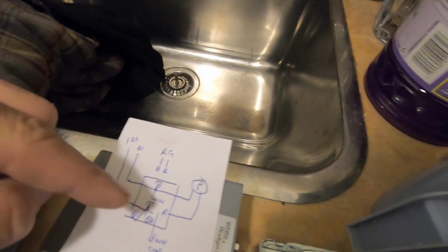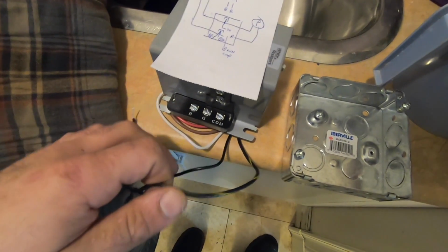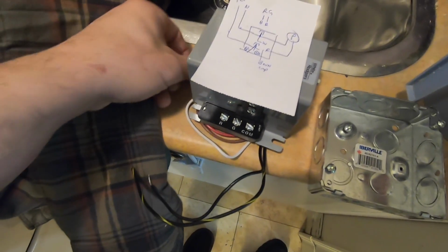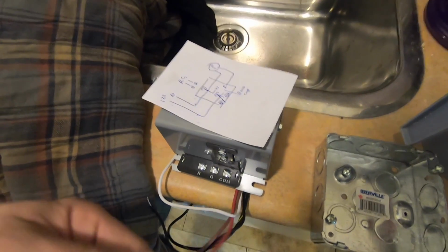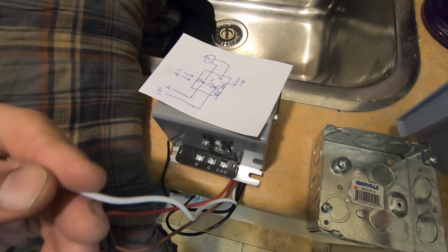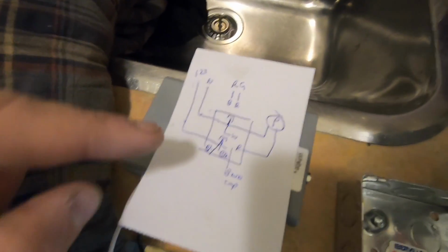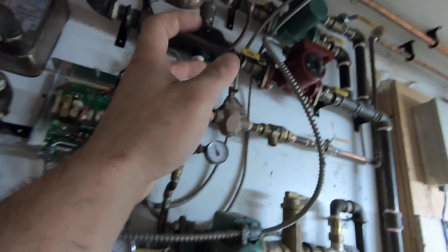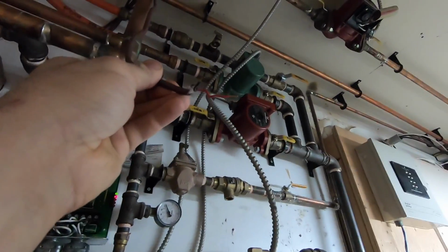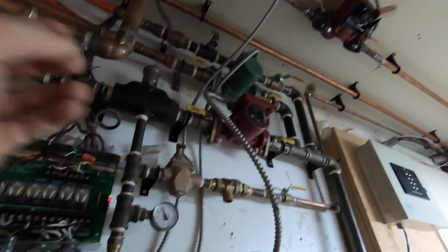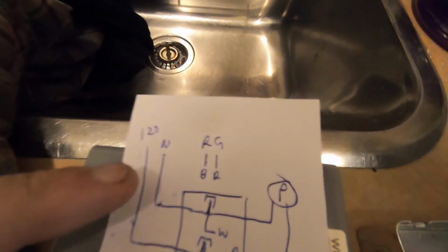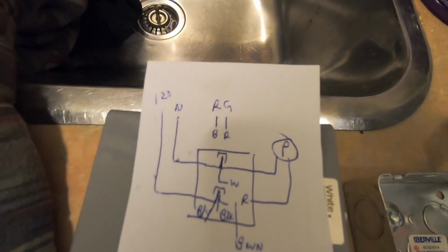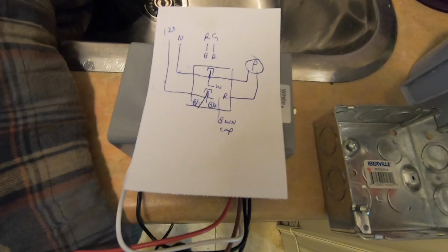So I got my power coming into the box. It's gonna get tied in to my black and yellow. Then my red is going to my pump, and all my neutrals are getting tied together, as you see. Then got a communication wire, my boiler call. So when there's a call, it's going to turn on the pump, and that's going to my R and G. Right there. So let's get to work.